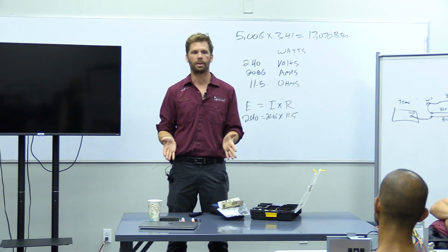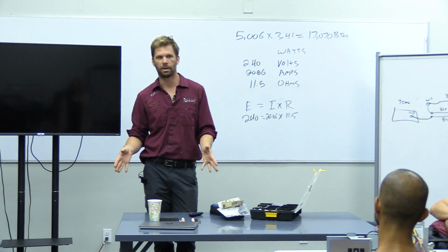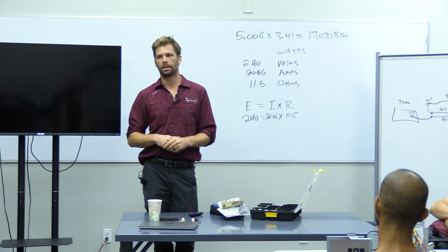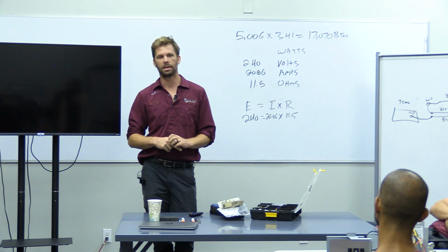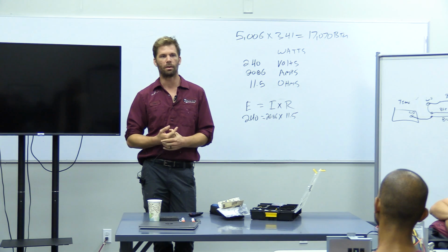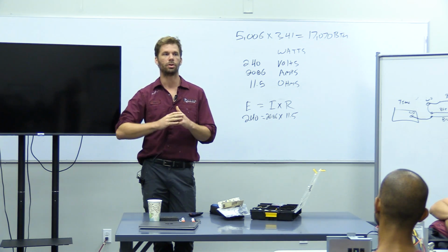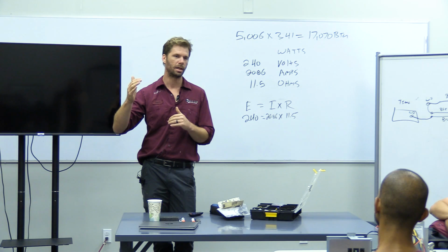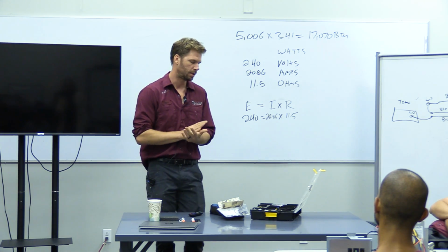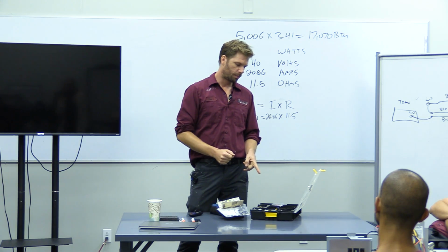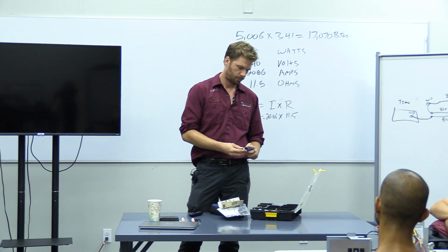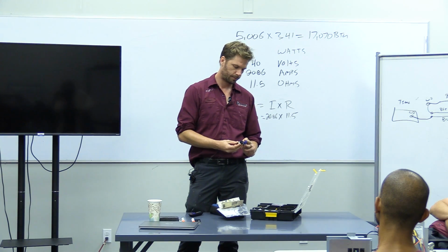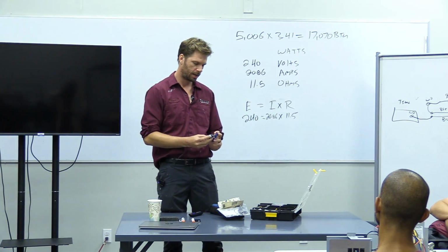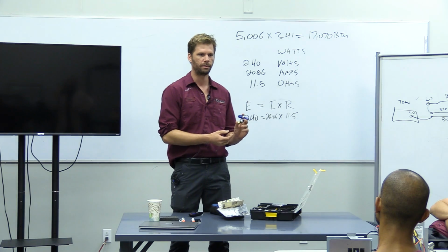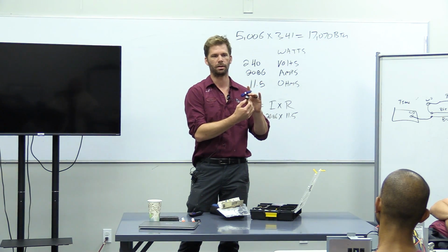Anytime you actually show up and your issue is a failed pressure switch, like a failed high pressure switch, again, stop and realize I can't just replace this switch or quote this switch until I find out what was causing that switch to open so many times that eventually it just stayed open. And that'll be the situation. Quick note on that, when you're doing a pressure switch, I have a couple in here. This one says it opens at 600 PSI, and then once the pressure comes down to around 475, so they're listed right on here, it'll close.